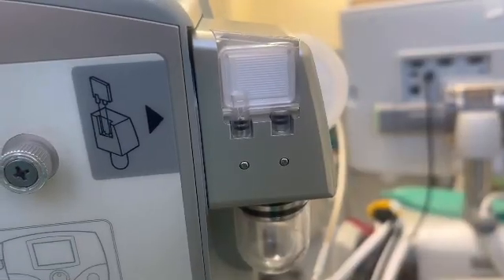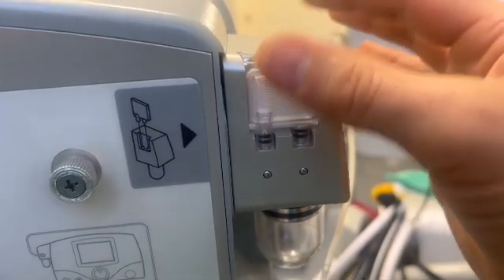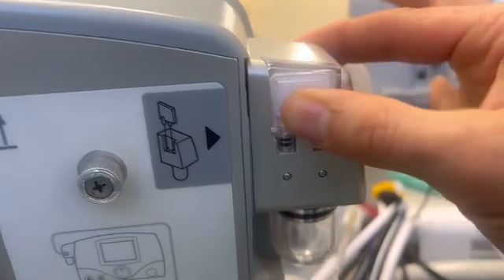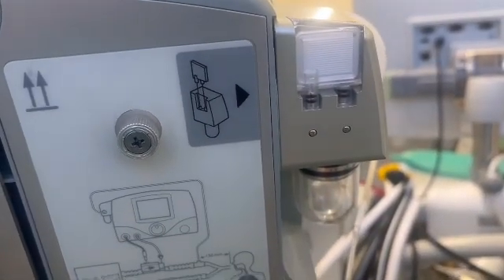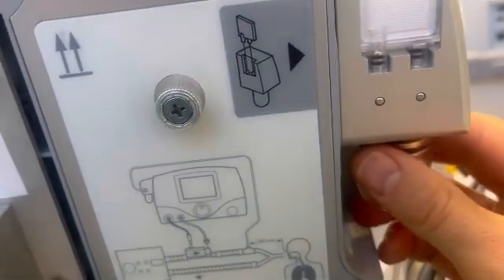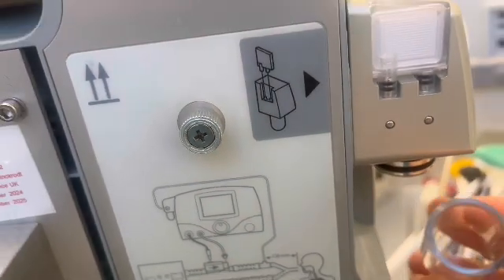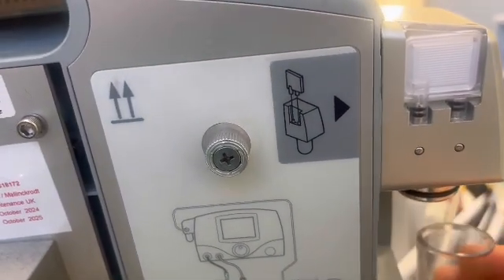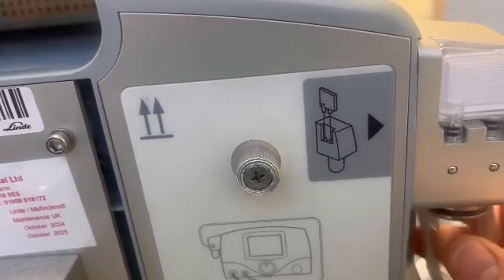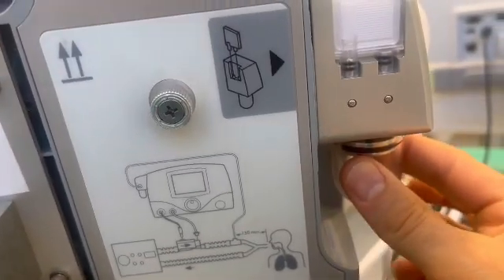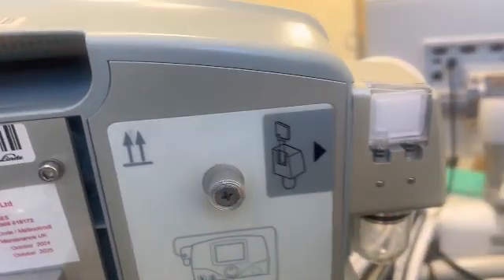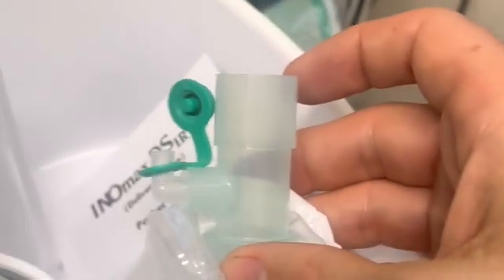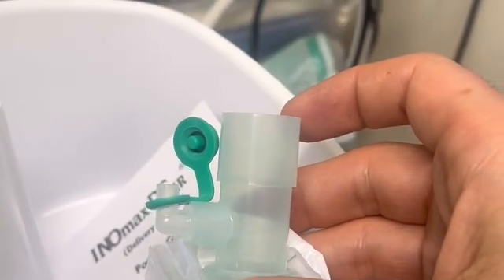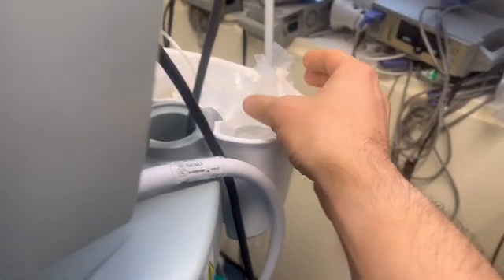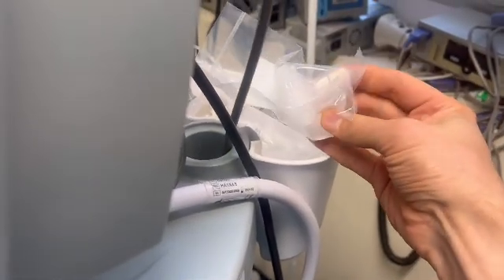You should make sure you have a water separation cartridge engaged properly into the machine. It sits above the water trap. The water trap is not disposable, and when it is taken off, it should be fixed back on, and you should make sure that you have a tight connection. When you've finished with the test circuit, you'll need a sample line adapter. This can be found at the back of the machine. You'll also find additional filters here.